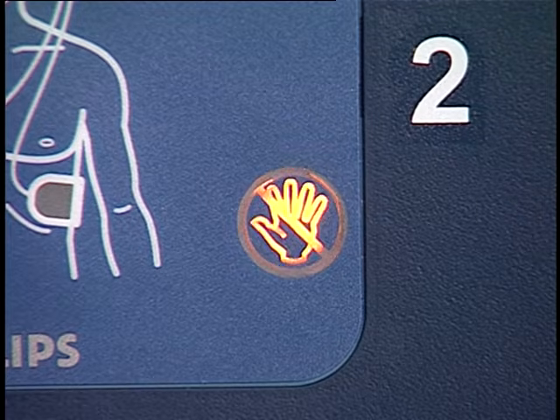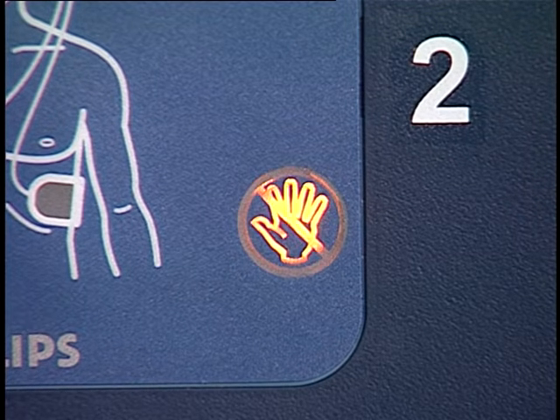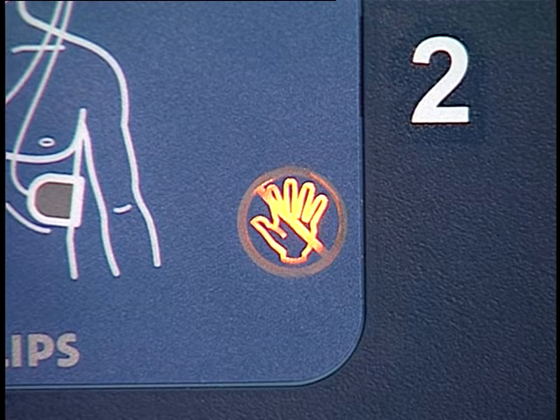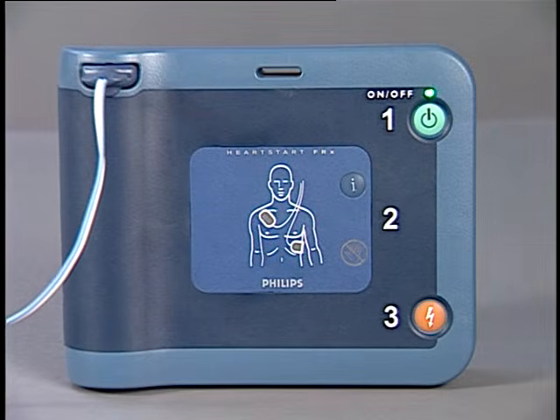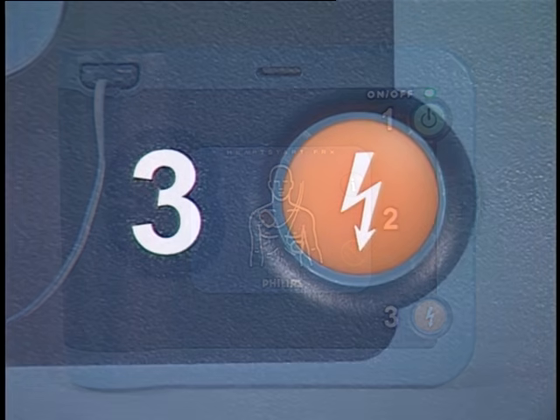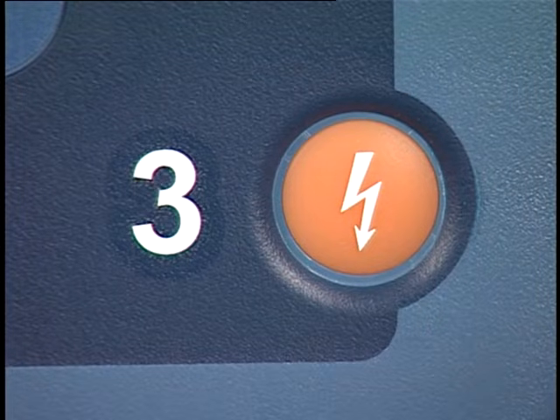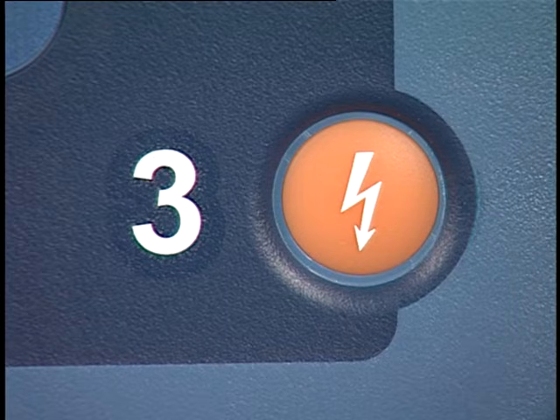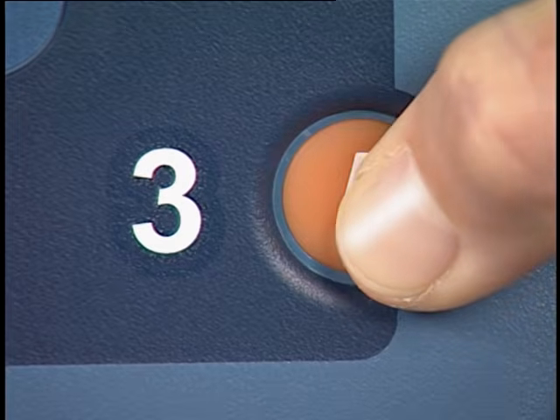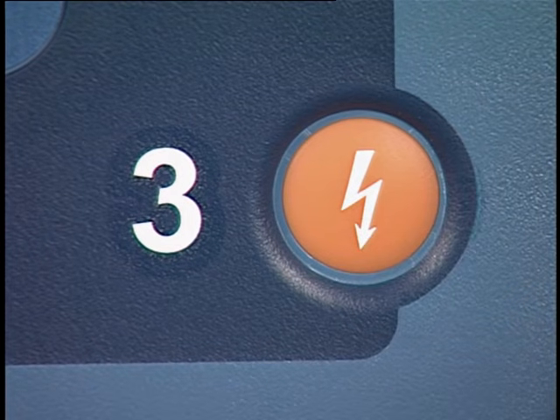The caution light automatically comes on when the FRx is analyzing the heart rhythm or delivering a shock, as a reminder that no one should touch the patient at these times. In the lower right-hand corner is the shock button. It is orange with a lightning bolt symbol. If a shock is needed, the shock button will start flashing and the HeartStart FRx will instruct you to press the button to deliver the shock.